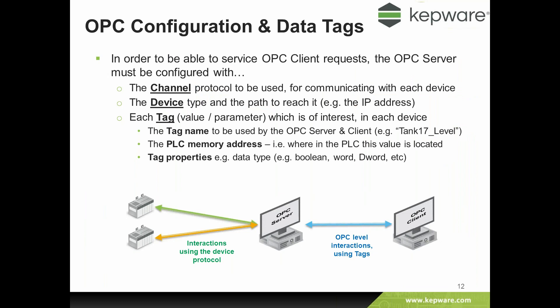In order for the OPC client to get data from the device effectively, the OPC server needs to provide a menu of available values, which is done through configuration. The OPC client makes a request upon the OPC server, which must then know how to locate that data and return the value. Within the OPC server, configuration is required: first, the channel — which specifies which communications protocol will be used — and each device in that channel must be given parameters such as the device type or PLC model and the unique path to reach it, such as the PLC's IP address.